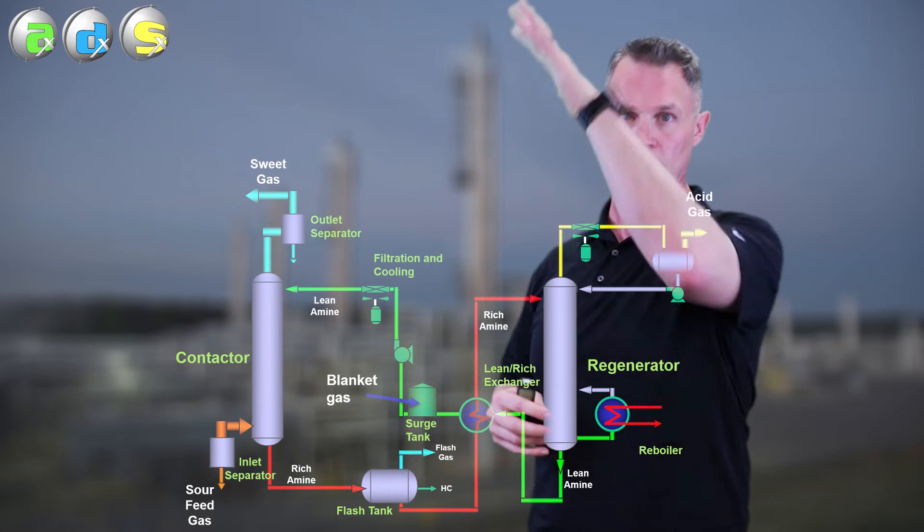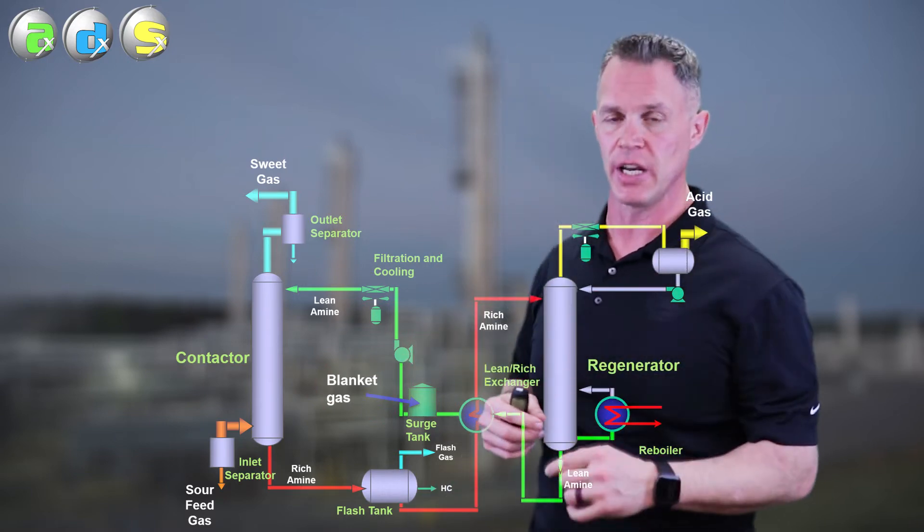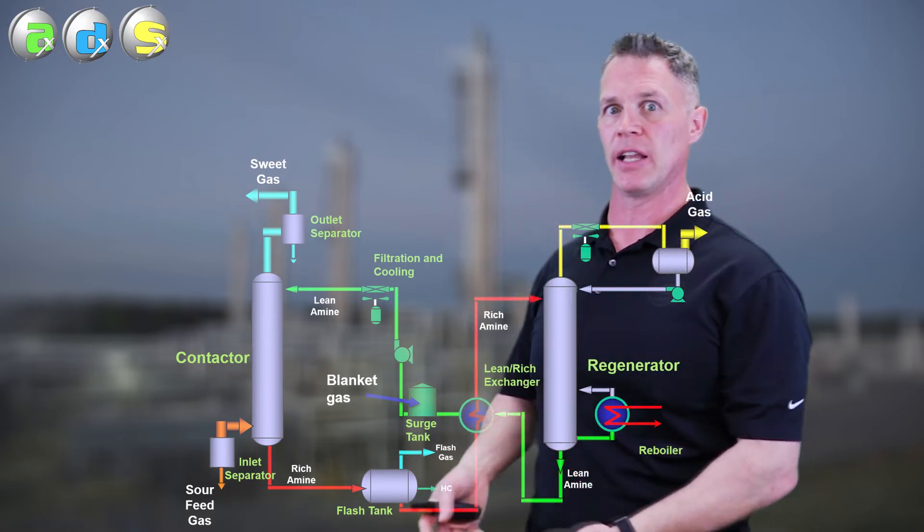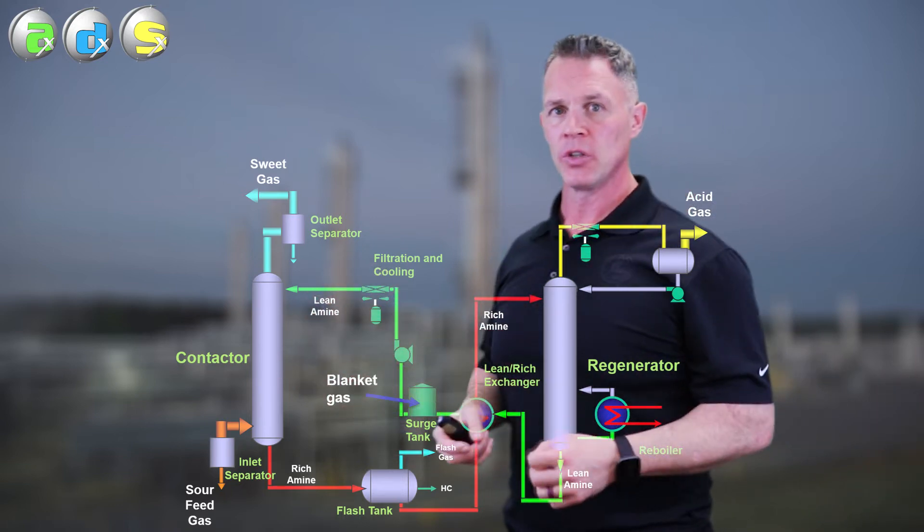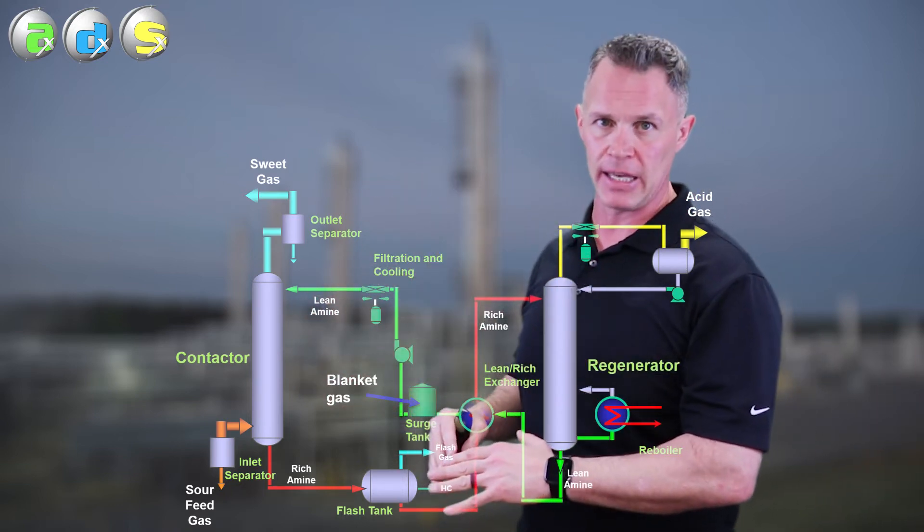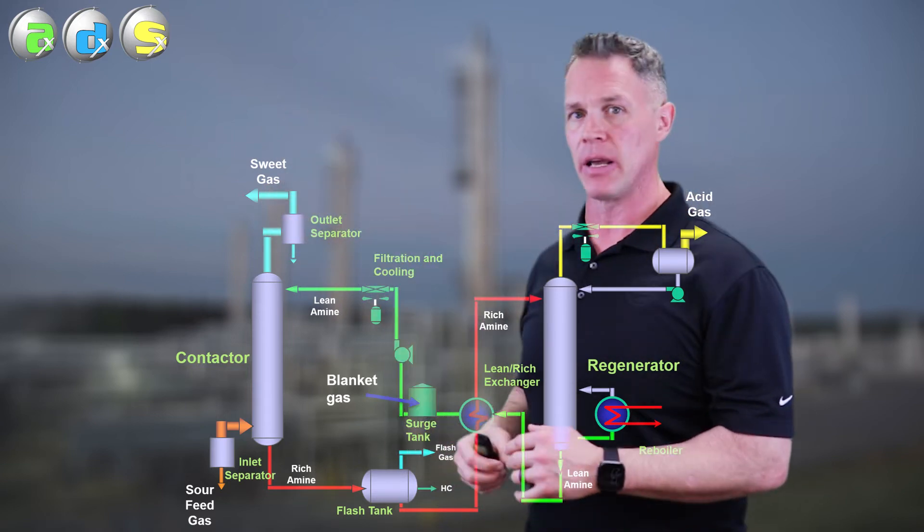The surge tank's whole purpose is to absorb surges in amine circulation rate, so that level does go up and down. The tank's just at atmospheric pressure, so if that level drops and we don't have blanket gas on, you will suck air into your amine system.